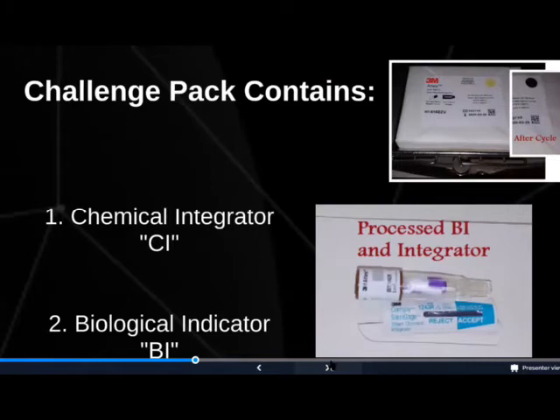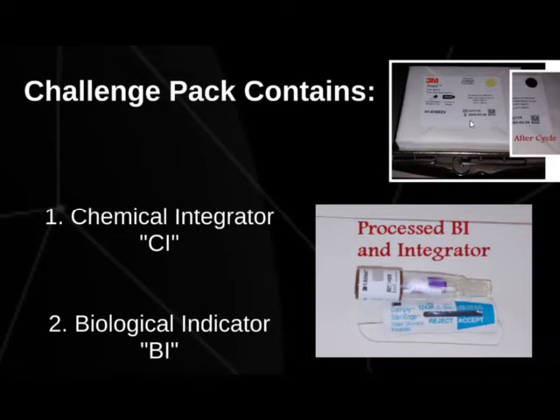So the challenge pack is the second test that's run on each autoclave. And you always want to check the expiration dates and lot numbers. Remember, the lot numbers always have to match your control. Inside the packs, it includes the chemical integrator, which says accept or reject, and then the biological indicator that has the actual spore inside of it. So that would be incubated.